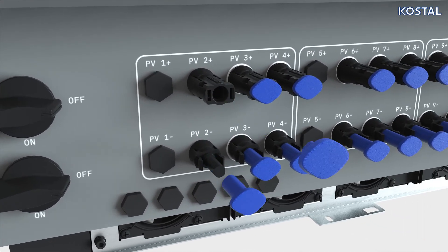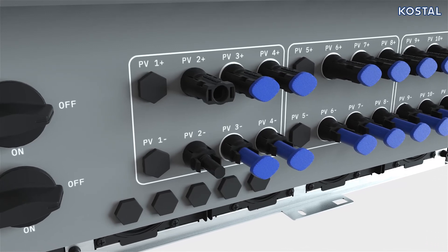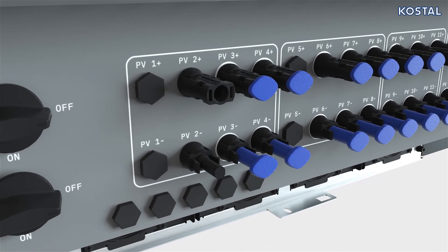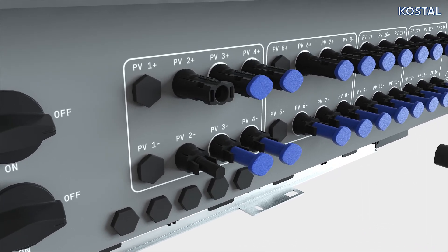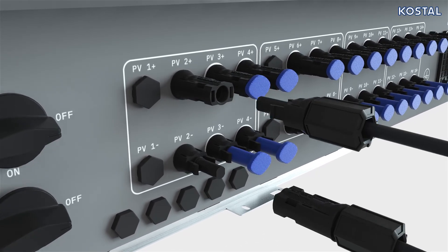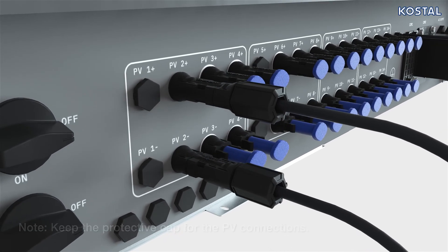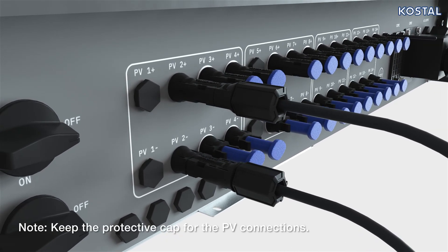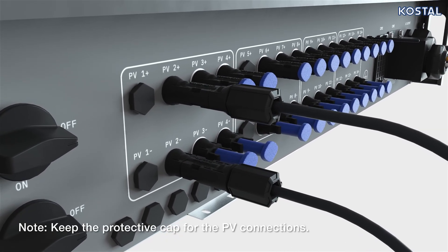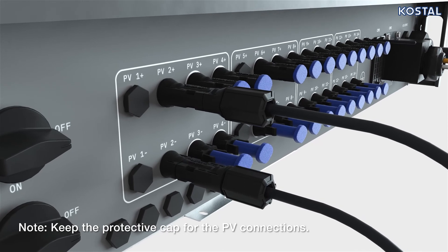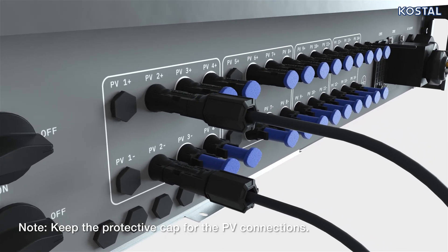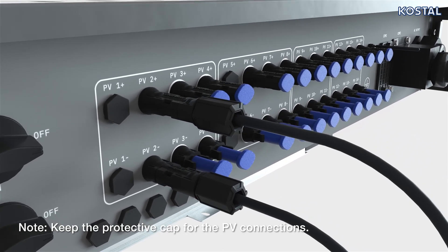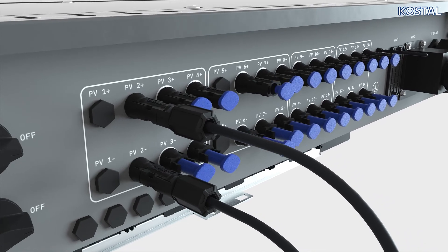Remove blue protective caps from connection sockets and plug pair of Amphenol H4 connectors onto the DC inputs until you hear them engaging. The order in which the connectors are connected should follow the white frame and markings on the device. Ensure an even distribution.